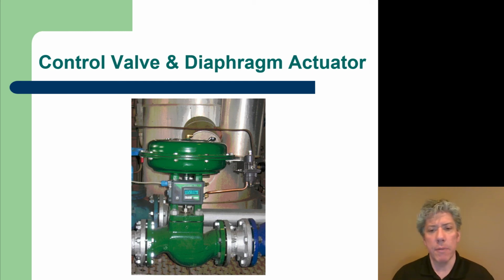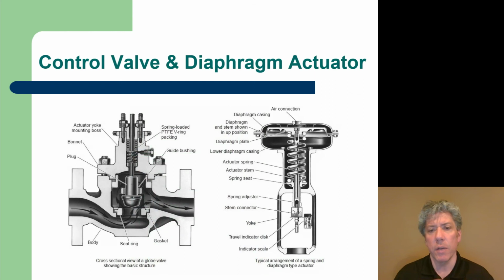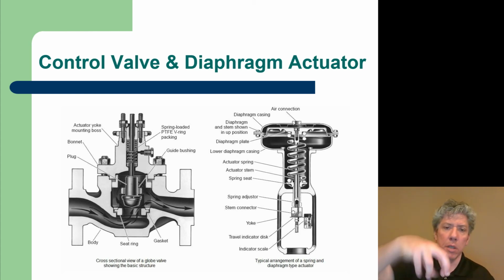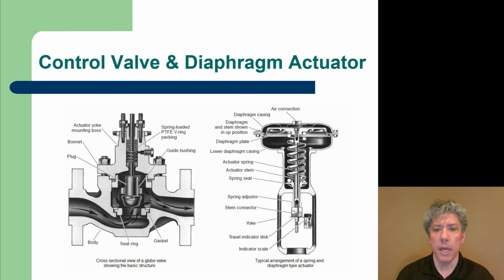Now, another type of valve that can actually be quite difficult to learn about, but that is very commonly used, is a control valve with a diaphragm actuator. Now, there are some differences in the valve itself, but this is just a different way of moving the stem in and out in order to control the valve. A cutaway will help you understand. On the right is the pneumatic actuator, and on the left is the valve body. Of course, the actuator would be bolted to the top of the valve, and the yoke, of course, would be bolted to the body of the valve. That's the outside piece there.